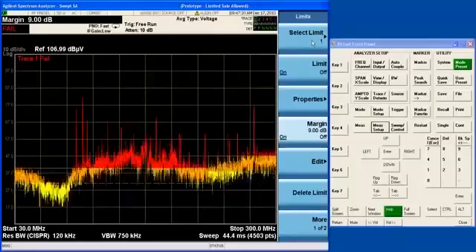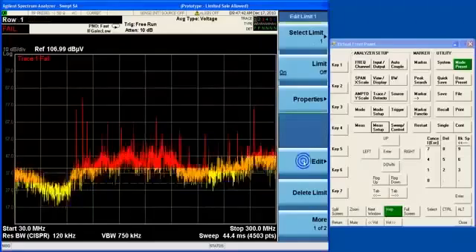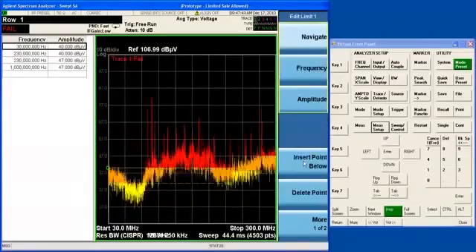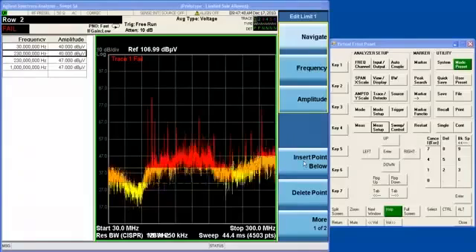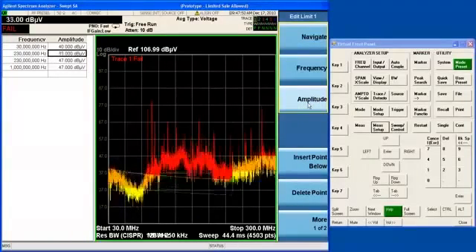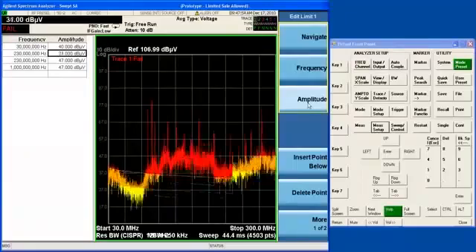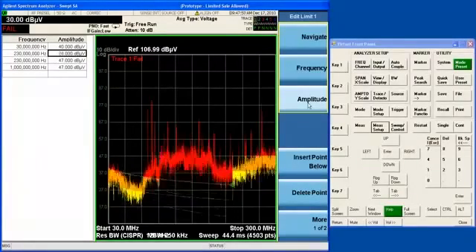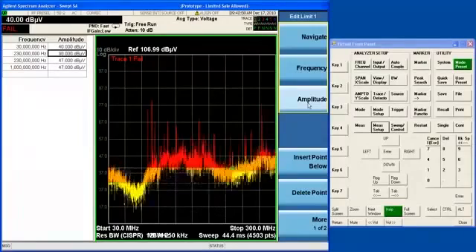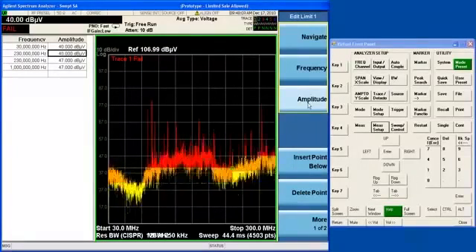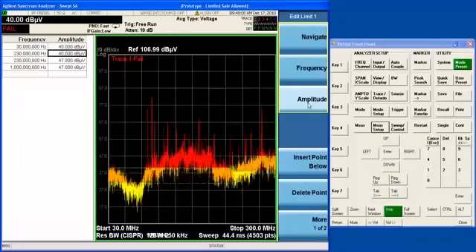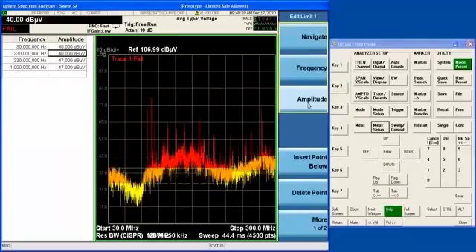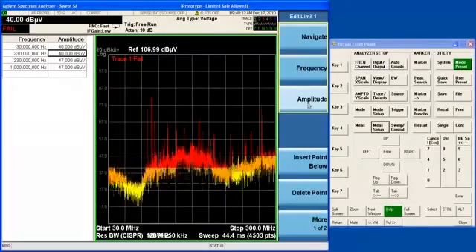That is a lot more points than were supported on our earlier analyzers. And there is a limit editor, just like there is an Ampcor editor, which lets you go into the limit array and adjust the frequency or amplitude of any of the points in the array. So you can see that it is very easy. I am turning the knob here to adjust the amplitude of this particular point in the limit array. It is very easy to adjust the values in a limit line using the limit editor. You can insert points. You can delete points. You can customize limits pretty much any way you like.